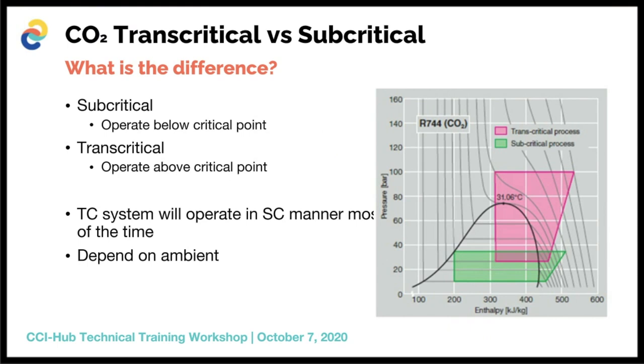I'd like to touch on CO2 subcritical versus transcritical operation. There is sometimes confusion around a plant being called a transcritical CO2 plant. The main difference is just in how it is operating. A transcritical plant can operate in a subcritical manner when the ambient is low enough — below the transcritical point of 31 degrees Celsius. Most areas have fairly cold ambient temperatures, so even a plant called transcritical will often operate subcritically.